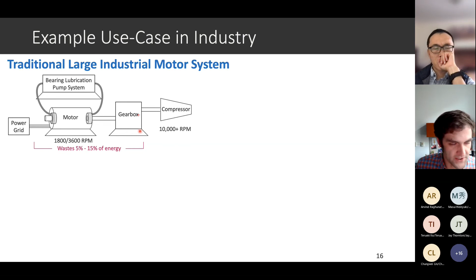One way to improve this classical system is, instead of directly driving your motor from the power grid, to introduce a variable speed motor drive. This is a valid solution, but the problem is that the variable speed drive introduces electromagnetic interference that tends to cause currents to flow through your bearings and wear them out. There are numerous studies on the lifetime reductions of bearings due to motor drives, and it can be upwards of a 50% reduction in lifetime when you add a motor drive.